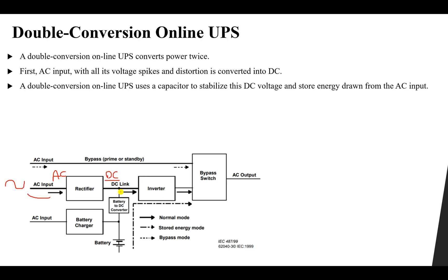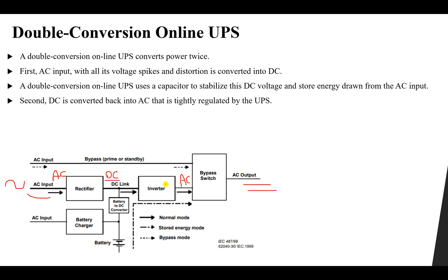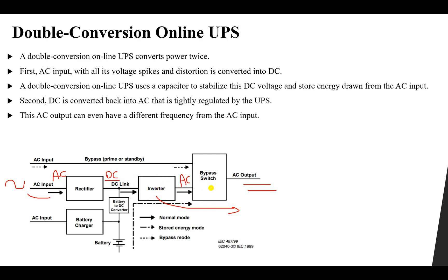The DC link stores energy drawn from the AC input. This DC is then converted back to AC suitable for our load using an inverter. This AC can have the same frequency as the supply or a different frequency, as we would like — by controlling the inverter we can control the output frequency. This is the double conversion process: first conversion, then second conversion.